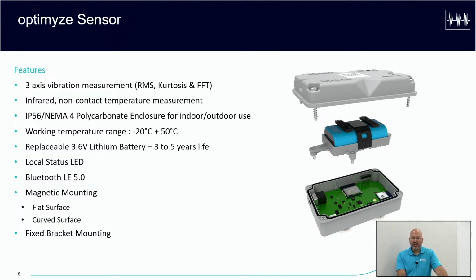The battery life, this is a bit unique to our solution here. A lot of the competitors' products on the market, once the battery fails, you do have to throw away the sensor and buy a completely new one. Not the case with ours. There's a few screws on the top of the sensor itself, then another couple screws on the battery. You take it out, replace it, you're back up and running. No data is lost. Really the only data that is lost is obviously the sensor's not taking readings while the battery is dead, so you just won't be capturing information during that time period.